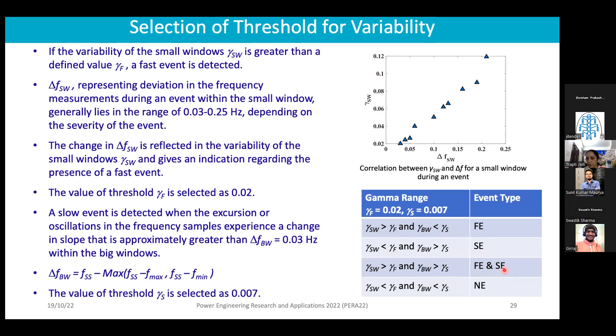Now we'll see different kinds of events and how we identified them. These are events with fast and slow dynamics occurring separately, from measurements recorded by the PMUs placed at Mumbai and Kanpur. This box A shows the fast event, and this one shows the slow event. You can see the variability here: whenever fast events are happening, gamma SW crosses above the threshold. When the slow event is happening, only gamma BW, the big window, is triggered. So transient events trigger only small windows, while slow events trigger only big windows.